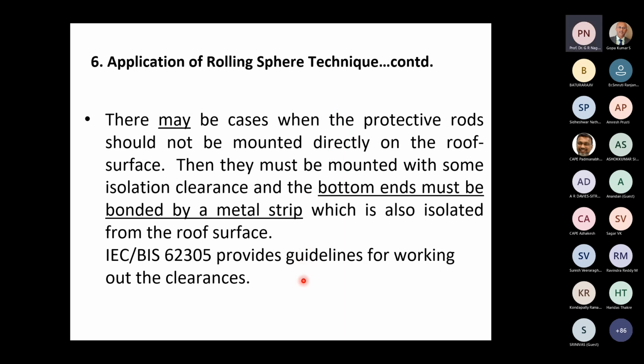Now, one question might arise. Whether it's the geometric method or the electrogeometric method, we have rods and meshes. Can the rods be located directly on the surface? That's a very common question. But there may be cases where, because of certain additional safety conditions, they have to be isolated from the top surface of the building by a small distance. These distances can be worked out using the guidelines provided by the standard IEC 62305. I'll not go into those details because they are quite involved, and there are several parameters to be considered. So I would request the audience to consult the standards in case they need.